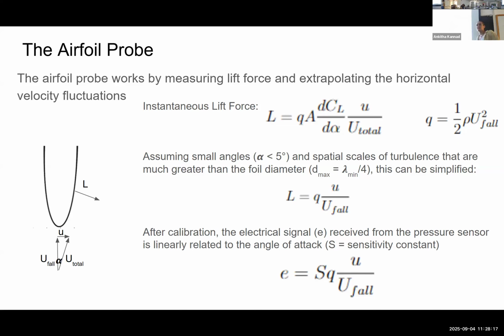And so how we do this with actual probes is we calibrate them. What you guys are going to see later is a tank that we use that creates a very laminar jet of flow. We take our probe and rotate it through a small angle of attack, and that way we get an electrical signal and a sensitivity constant. So what we're measuring for is this constant that allows us to translate between the signal we get and the angle of attack. This is theoretically supposed to be a linear relationship, and it is pretty close to one. But for every single probe that we make, we run it through the calibration tank, because based upon the microscopic structure of the piezo material, this sensitivity constant will be different for each probe. So that's why we have to calibrate them.